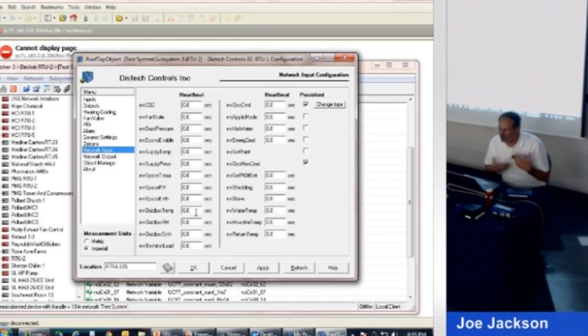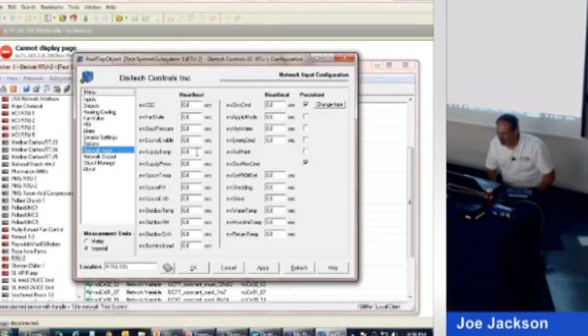An NVI is a network variable input. This is information coming into the controller from other controllers. And if you want to send that, how often does it go out and look for it? Let's say there was a VAV box that had a CO2 sensor on it, and I wanted to get that information every 20 seconds. That would force it to go out and look every 20 seconds for that information, if you were sharing a lot of data between controllers.